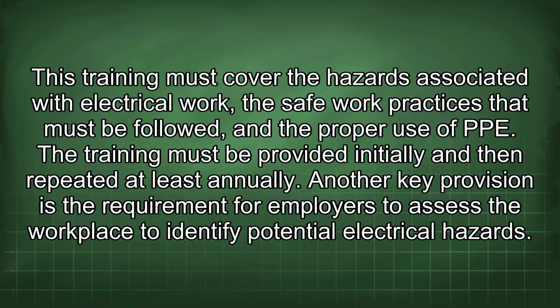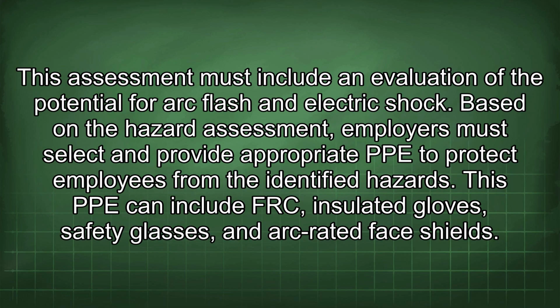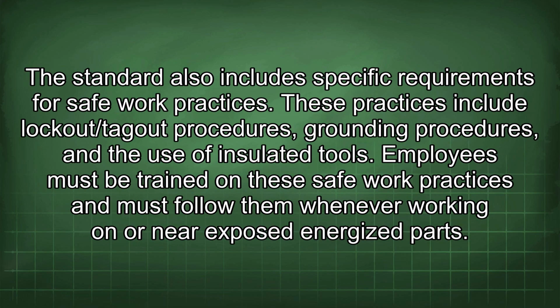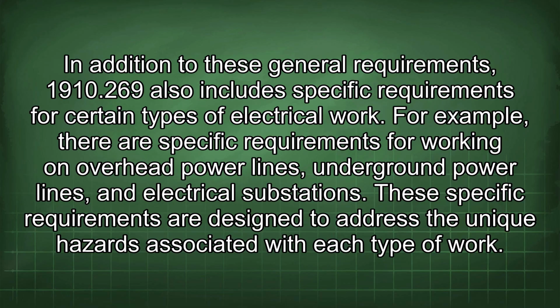Another key provision is the requirement for employers to assess the workplace to identify potential electrical hazards. This assessment must include an evaluation of the potential for arc flash and electric shock. Based on the hazard assessment, employers must select and provide appropriate PPE to protect employees from the identified hazards. This PPE can include FRC, insulated gloves, safety glasses, and arc-rated face shields. The standard also includes specific requirements for safe work practices. These practices include lockout/tagout procedures, grounding procedures, and the use of insulated tools. Employees must be trained on these safe work practices and must follow them whenever working on or near exposed energized parts.